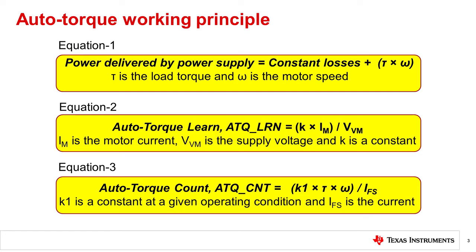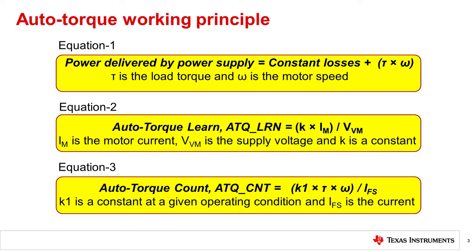The auto torque algorithm obtains information about the load torque by monitoring the power delivered to the motor using V and I values of the motor windings. The constant losses are modeled by ATQ_LRN, the auto torque learn parameter. The auto torque learn parameter is directly proportional to the coil current. This is represented by equation 2.